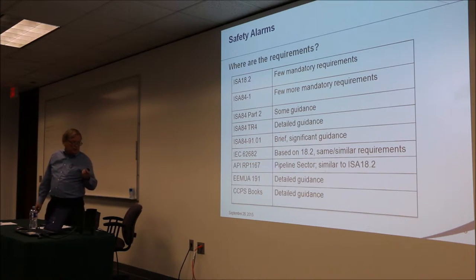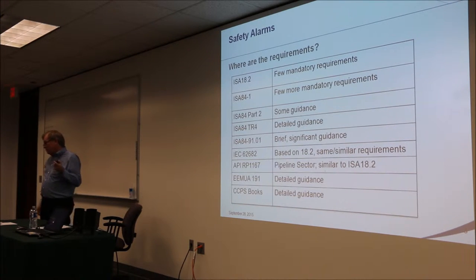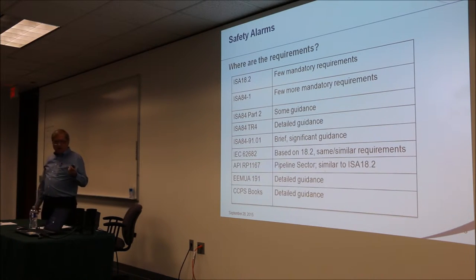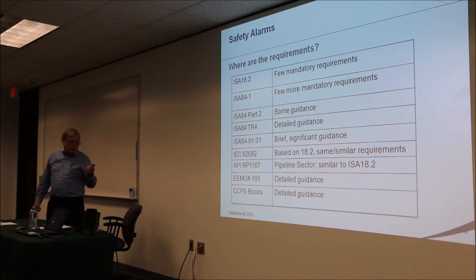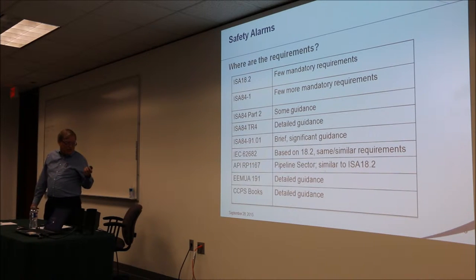9101 has a brief document with very significant guidance. IEC 62682 is the IEC version of the 18.2 alarm management standard, issued recently. Based on 18.2, there's not a whole lot of difference from the standpoint of safety alarms — there are more shall statements, but it's really not a significant difference. 1167 is a pipeline sector alarm management recommended practice, very similar to ISA 18.2.